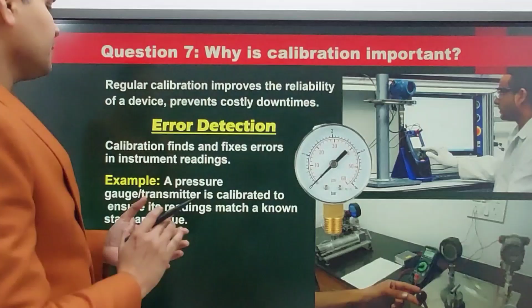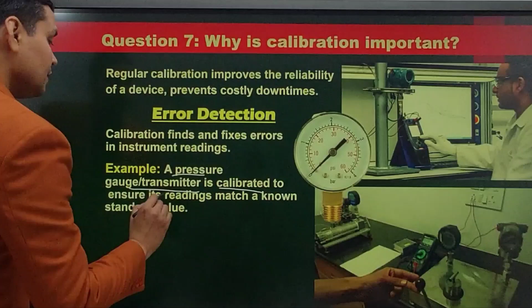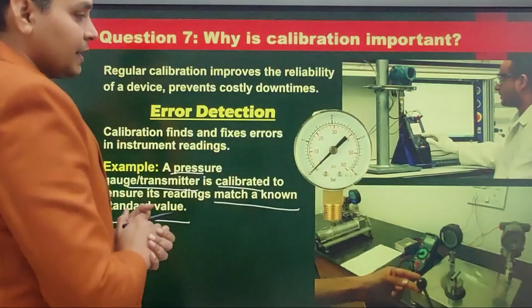Let's understand it with an example. Suppose we are calibrating a pressure transmitter or a pressure gauge. A pressure gauge or pressure transmitter is calibrated to ensure its reading matches a known standard value. Here you have to remember one important point: the transmitter or gauge is calibrated to match its reading with a known standard value. Let's understand how we will do calibration. If we are calibrating a pressure gauge or a pressure transmitter, we will use this instrument, known as a deadweight tester.